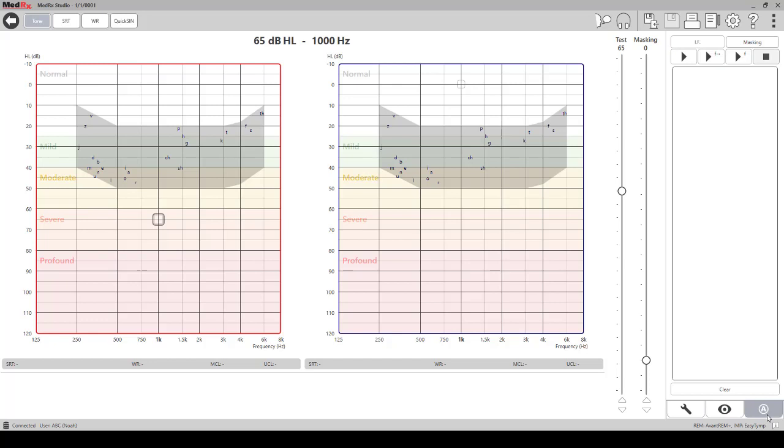The automated audiometry icon allows you to access the automated testing mode. The audiometer can be set to automatically do a complete test or screening for air and bone conduction testing. When the test begins, the test automatically proceeds to the next level as soon as the patient responds by pushing the response button. This will continue until the test is complete.